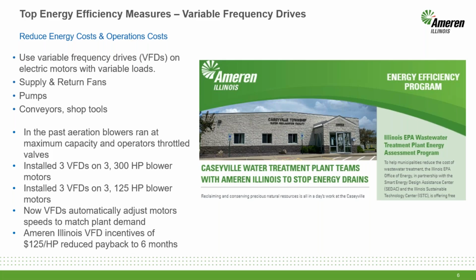Another top measure to consider are variable frequency drives, which control motors based on loads. You want to use these where you have motors running at 100% and where the load varies, so you have opportunities to throttle the motor based on demand. Variable frequency drives should be considered for supply and return fans, pumps, conveyors, and shop tools.